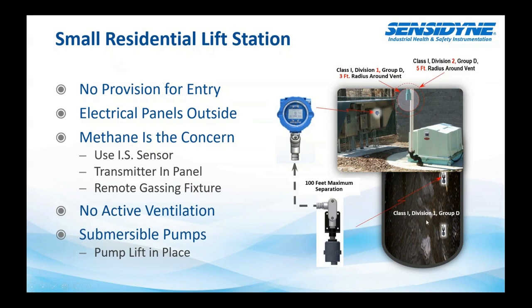But here's an example, a picture of a small residential lift station. No real provisions for entry. We would mount the sensor remotely from the transmitter into the wet well. This is one way of doing it. Obviously, there are some hazards introduced here in the operation of the sensor because it is in this moist environment, with a lot of corrosive gases and things like that. But it is one way of doing it, with remotely mounting it. We would put the transmitter then out here on the control panel. Methane, obviously, like I said, is the concern. We can use an IS sensor. These sensors are all IS, so when they're in the wet well, there's no risk of explosion from the sensor. And that's the scenario, there's no active ventilation.